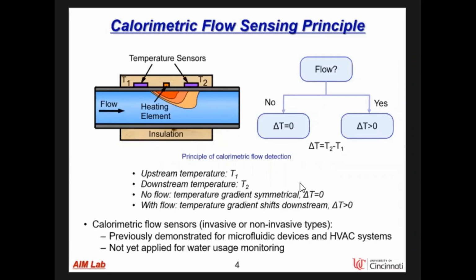The principle of calorimetric flow detection is illustrated in this figure. Two temperature sensors are placed symmetrically beside a heating element on the pipe. The one on the upstream side is T1, and on the downstream side is T2. When there is no flow, both upstream and downstream sensors record the same temperature, that is, T1 equals T2. When there is a flow, the temperature gradient is shifted downstream, causing a temperature difference delta T, which is T2 minus T1, being greater than 0. This delta T can therefore be used for water flow detection.